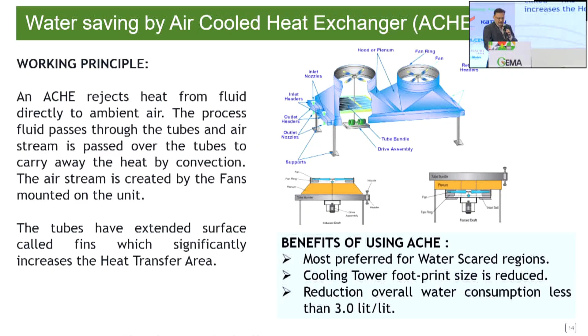Also, during environmental clearance, there are very stringent norms being put by the agency for water saving, and wherever there is a very stringent water saving norm, you can use ACHE as a technology for saving water. Basically, an ACHE uses ambient air for the cooling purpose, and with that the overall water consumption in your plant can be as low as 3 liters per liter. This is a typical water saving that you can achieve in, say, a 200 KLPD plant by using ACHE. You can achieve almost 60% water saving in an ethanol plant by using ACHE.